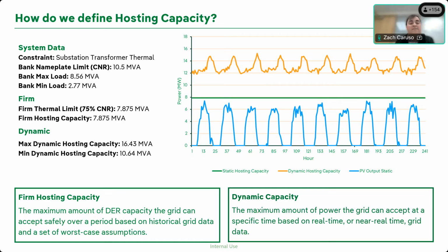So with that in mind, I'm not going to go into the details of this example, but the point is that if we have a bank rating of 10.5 MVA, we would only allow 7.875 MVA to interconnect firm to that, but we could have as much as 16 MVA available. That's a big delta of potential to install more capacity and get more PV generation, and that has benefits for the system, for ratepayers, and ultimately speed benefits as well. If we don't have to build that upgrade to increase capacity to get more DG on, we can get there sooner.